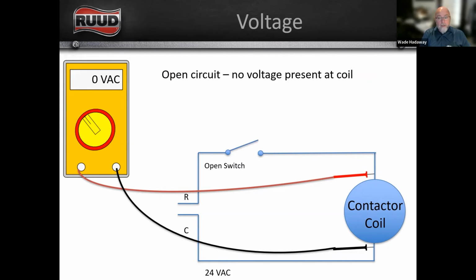With the switch open and I check there at the contactor coil, I don't have any voltage, right? And it might not be that the switch is open. You might have a broken wire, right? That's a very common repair. You get a customer complaint that the system's not working, right? So you go out, the contactor's not closed, you pull out your meter, you check across the coil, you don't have any voltage, and you start looking for an open circuit somewhere. It doesn't have to be a switch, it could just be a broken wire.